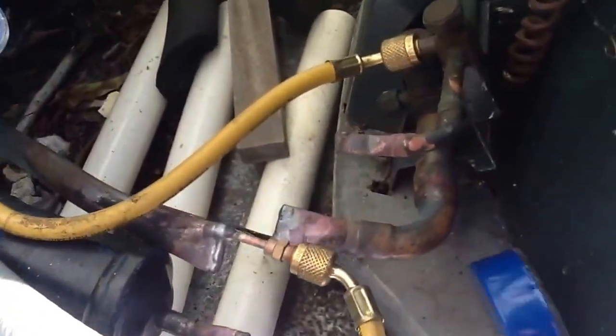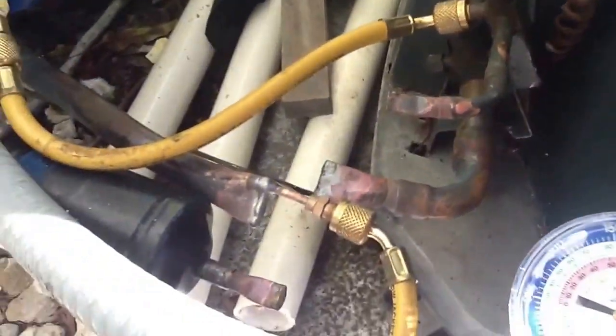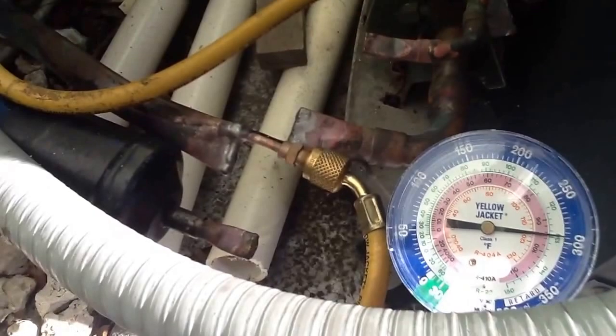We did the same thing with the line set. We put a test port in the line, soldered it off the other end, looped it in the attic, and put it on 300 pounds PSI.